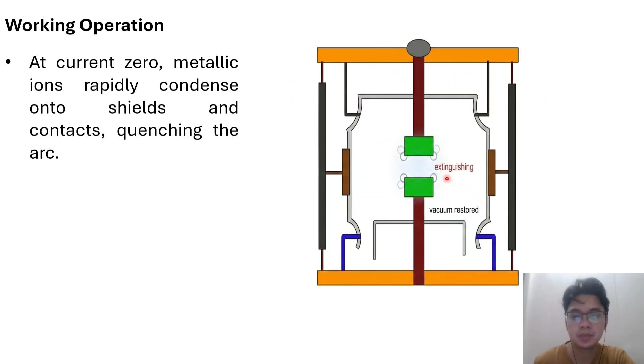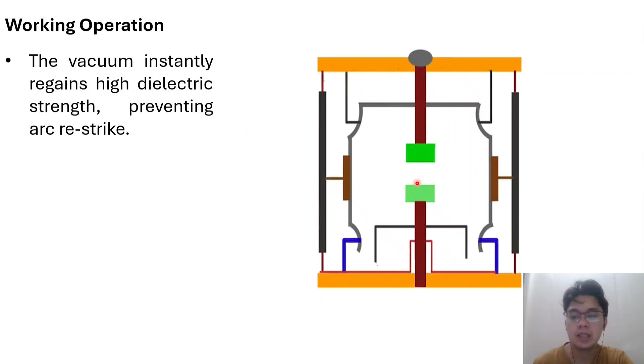So because of this very fast recovery, vacuum circuit breakers are highly reliable and effective in protecting electrical systems. Also, because of this fast and efficient interruption process, the vacuum circuit breakers offer several advantages. VCBs are compact in size, so they require less installation space, and they also have longer service life because the contacts experience very little wear during operation.